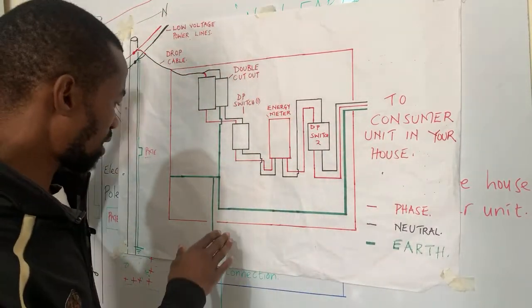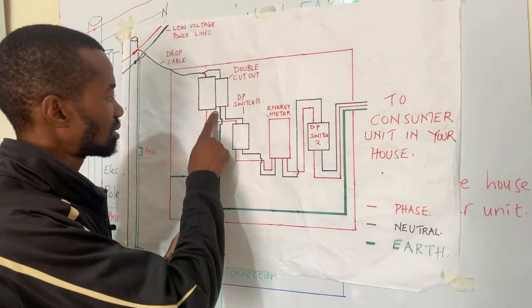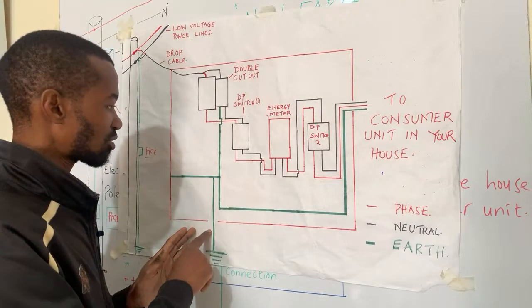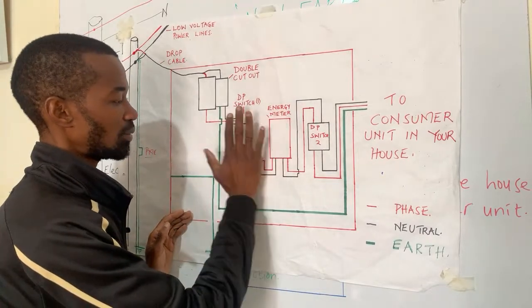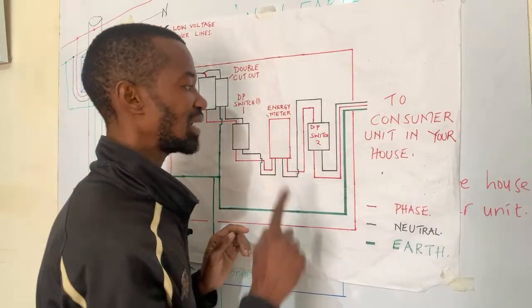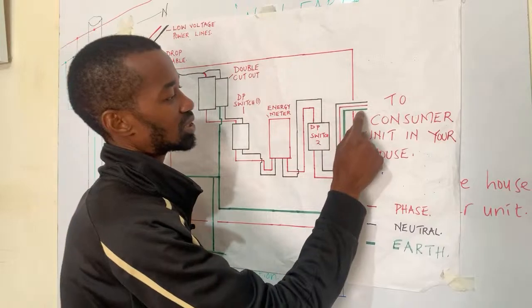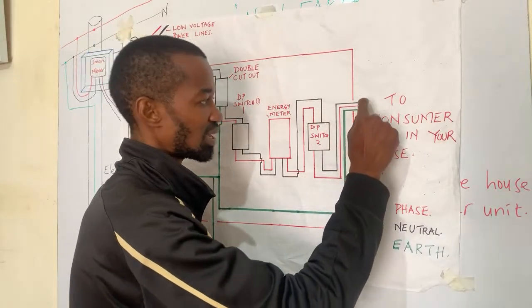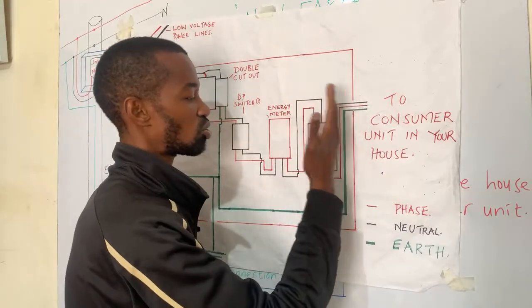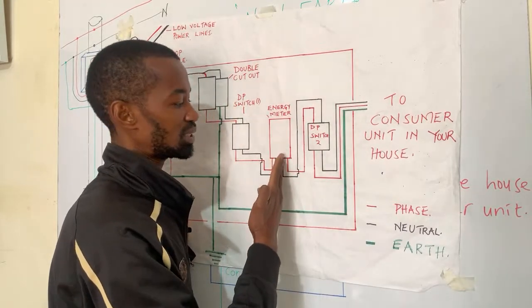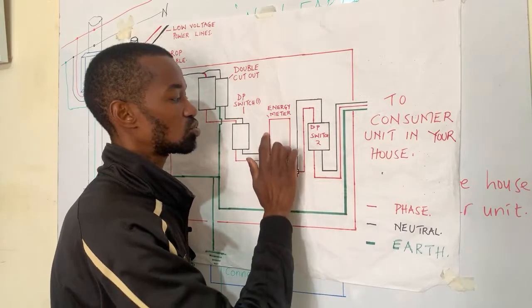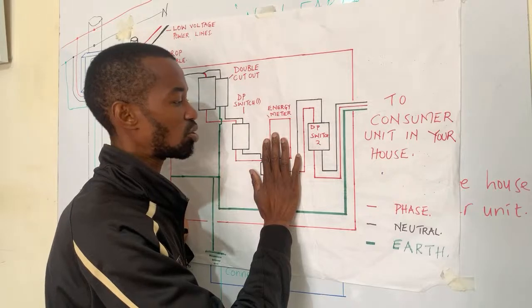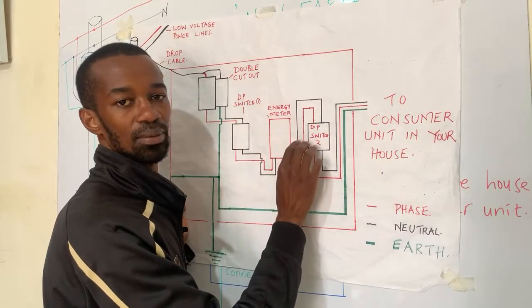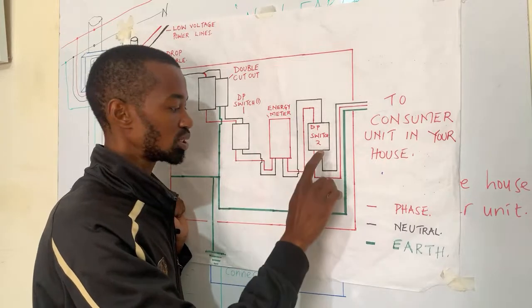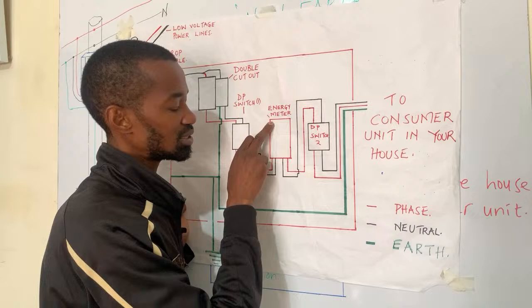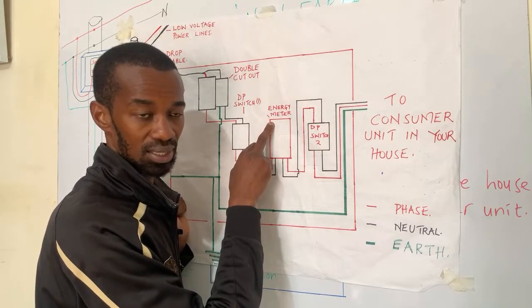All right. So I hope you have understood up to this particular point, including bonding the neutral and the earth connection. That is before the energy meter. That is very good. But again, an issue will arise if you try to bond the neutral and the earth at the consumer unit or after the energy meter. Some energy meters will sense that as a fault, and that is why you will find that there is a fault that is now referred to as a bypass. This one is indicated by the CIU, the customer interface unit, that is feeding the energy meter with tokens. That one that is normally in the house.